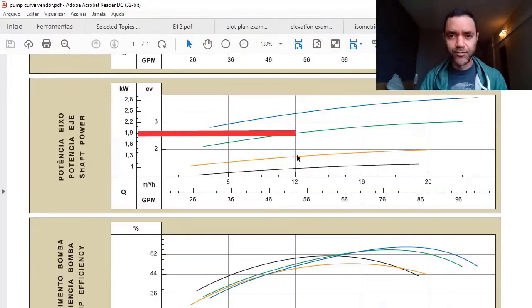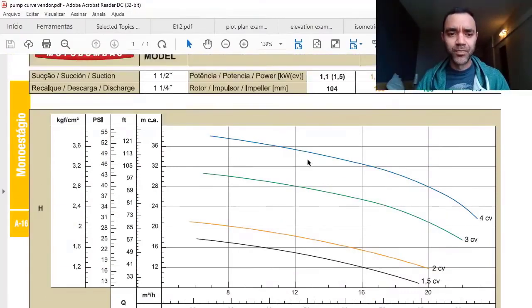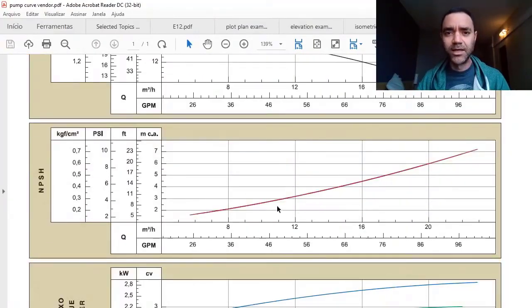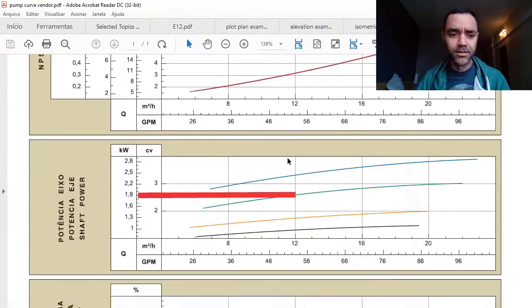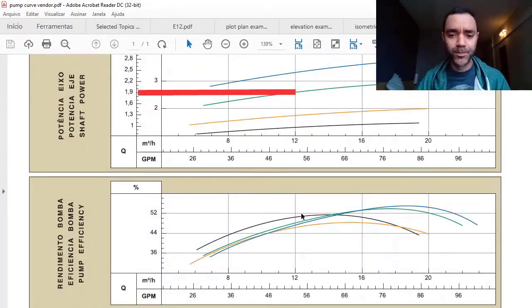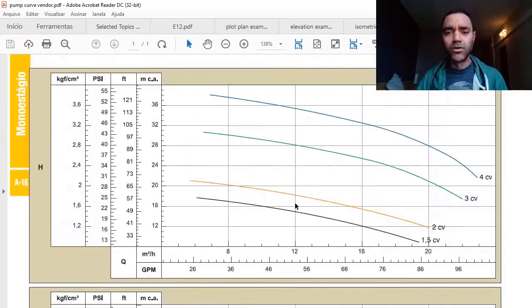You get the specifications to the vendor, the vendor will reply with a technical economical proposal, and one of the documentation that must be available to you is the pump curve. With the pump curve, you will verify the flow and head, you will verify the NPSH required, you will verify the shaft power needed for your pump, and you will verify the pump efficiency.